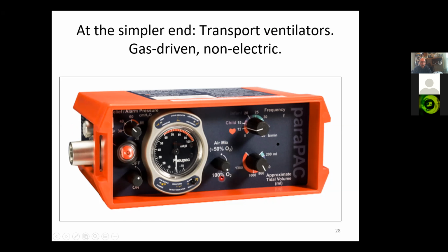It can be set to 100% oxygen. Well, of course it can. It's connected to an oxygen tank, and that's what's powering it entirely. You can dial it down to about half oxygen, but you can't get it lower than that. This doesn't have a second tank of oxygen for a blender. It can entrain some air, and therefore nitrogen, to reduce the oxygen concentration, but only down to a limit. It still has to have enough total power source to run the whole thing.